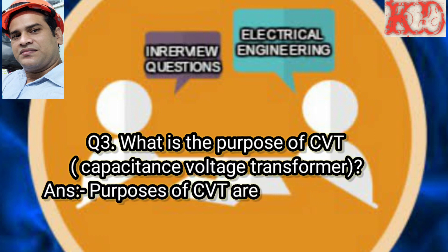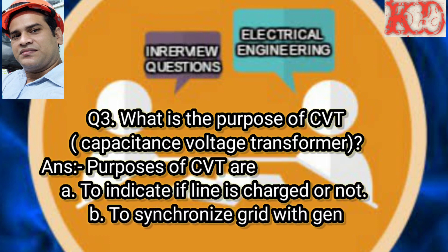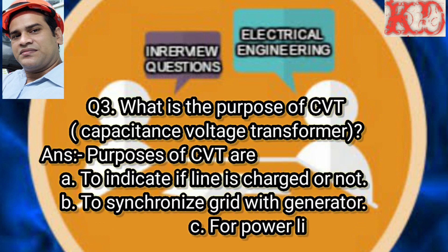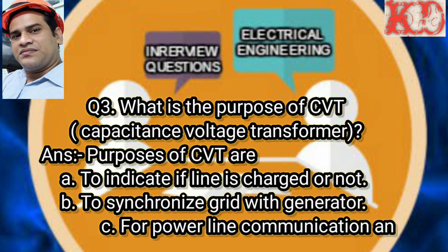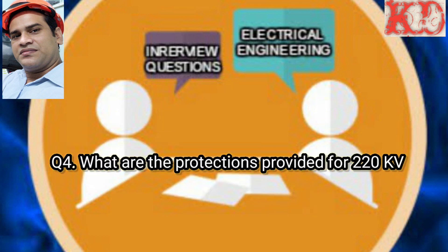Question number 3: What is the purpose of CVT? CVT stands for Capacitance Voltage Transformer. The purposes of CVT are: first, to indicate if the line is charged or not; second, to synchronize the grid with generators; third, for power line communication and carrier tripping.